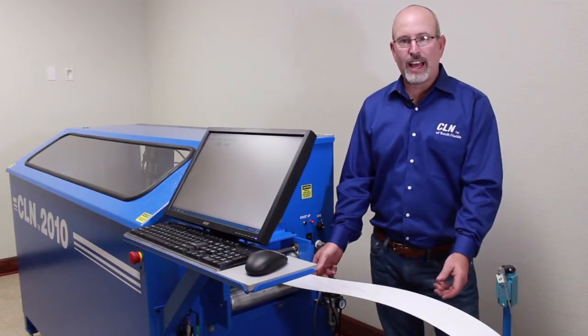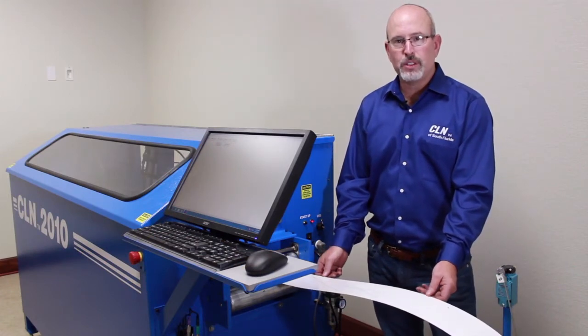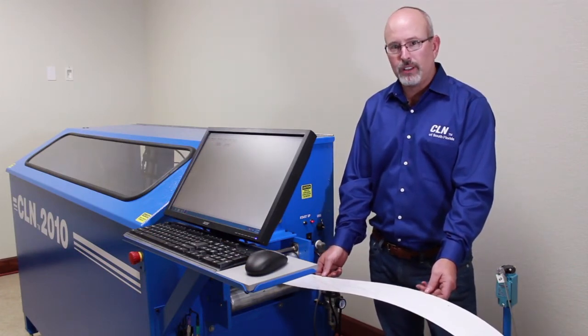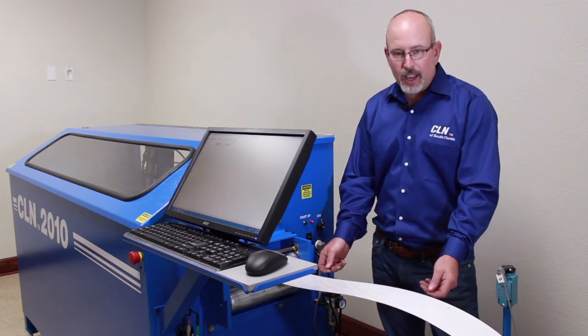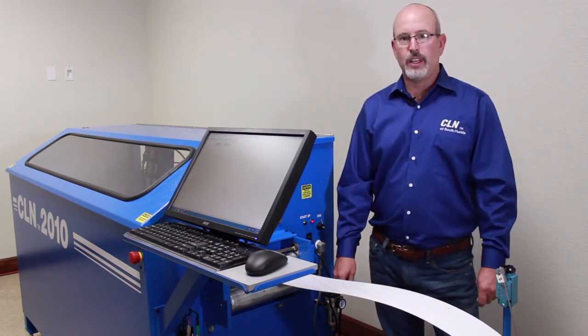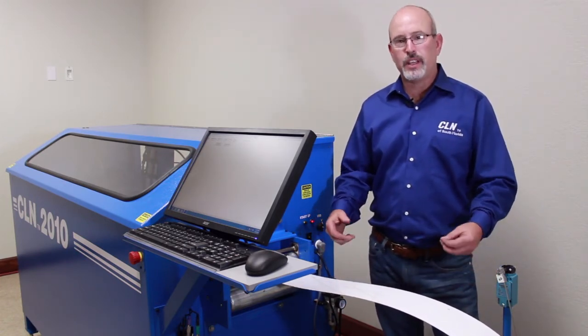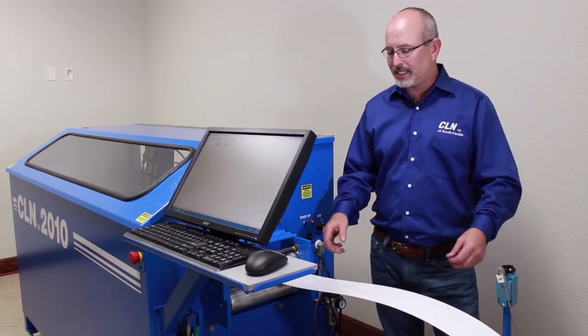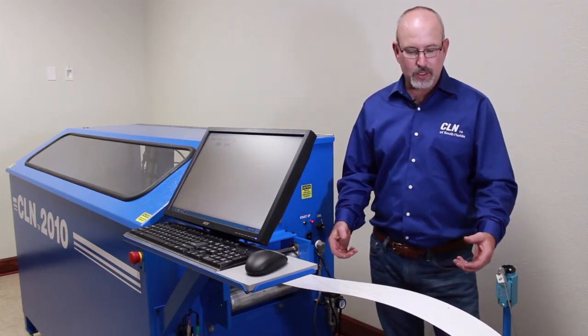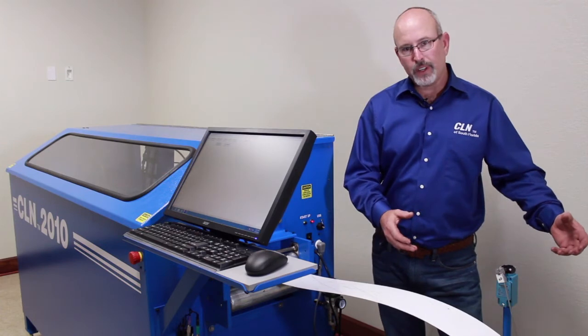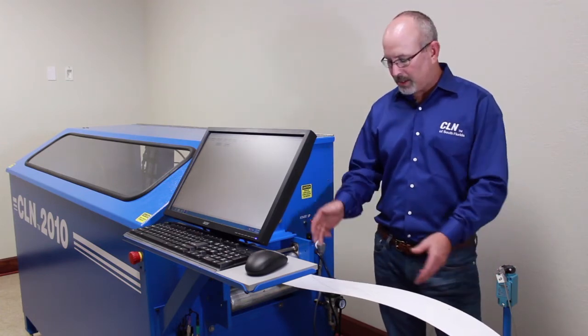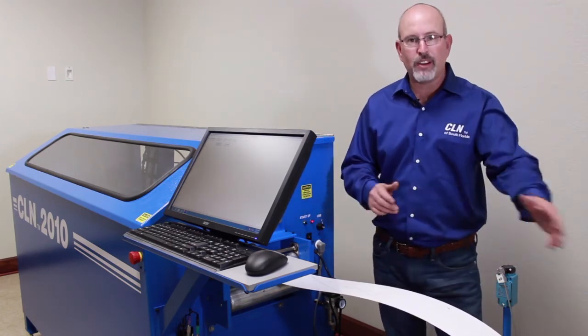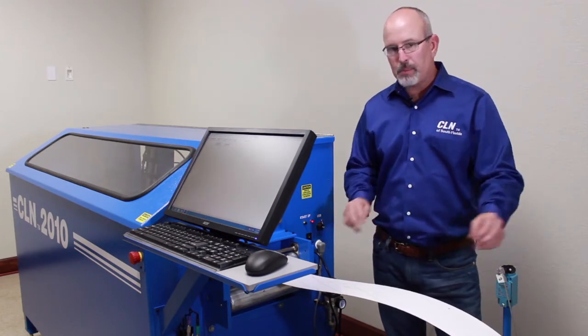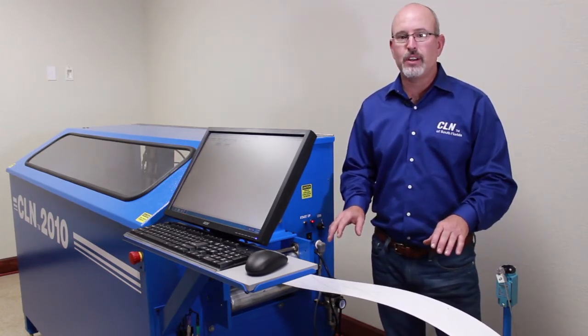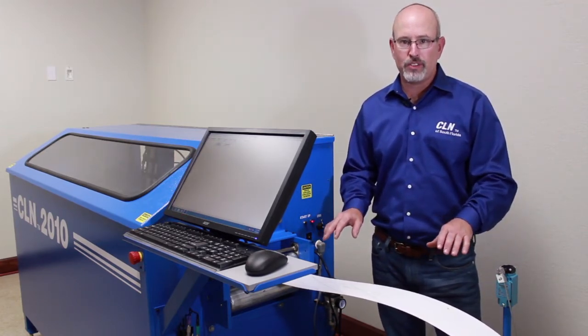There is another value to adjust. If you notice your machine starting to work slowly or make a lot of tiny little moves, then you're going to have to go in to the step motor calibration. It is exactly the same way that you adjust the encoder counts. You do it the same way. You're going to put a mark, you're going to measure out 48 inches, and you're going to make a move. But this time, you're going to use uncalibrated move in the program.